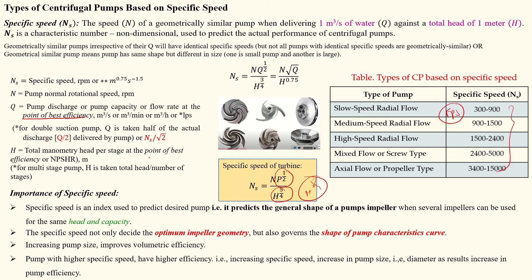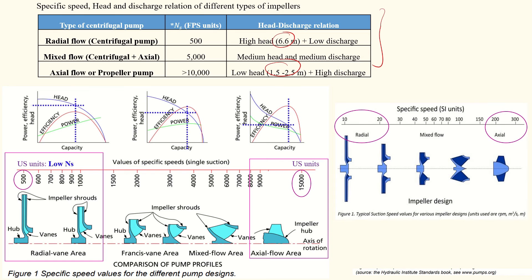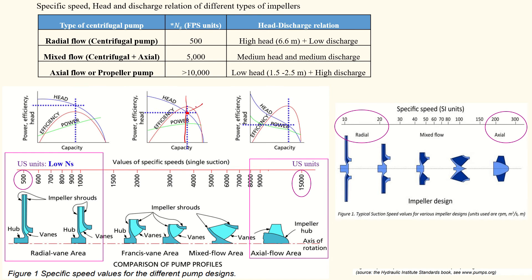Q and H must both be calculated at the best efficiency point (BEP). Looking at the head-discharge curve: as Q increases, head drops. At peak efficiency, there is a corresponding head value — this defines the best operating point. For axial and mixed flow pumps, as head reduces and efficiency increases, that lowest head at peak efficiency point is the best operating point.